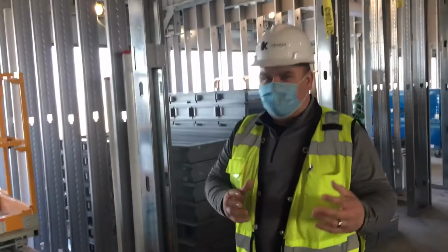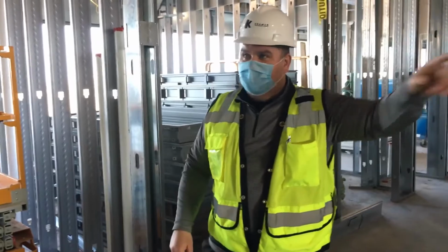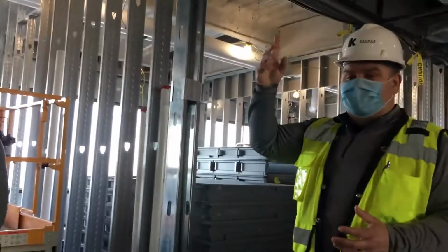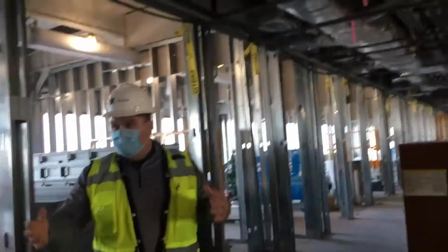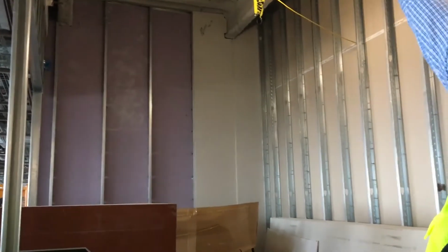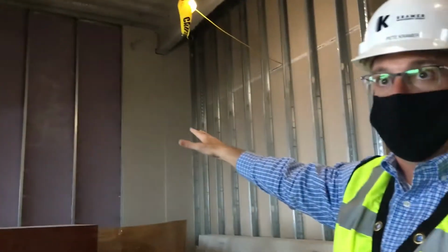We had some of our facilities management team come out, look at these. We saw stuff that we did change, access to valves, like, hey, we're never gonna be able to reach that valve over there because there's 3 pipes in the way. But you need that for prefabrication, right? There were I think like 260 of these racks roughly that we built. And you don't want to run ahead and build 260 of these things and find out you were a couple inches off on every one of them. So even just a simple rod like that, that's all modeled 3-dimensionally, and as soon as that floor slab's hung, they can shoot that anchor in, drop those hangers, and run through. Before all these studs are in the way, all the hangers are hung for the whole project.